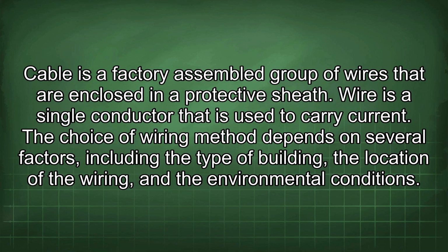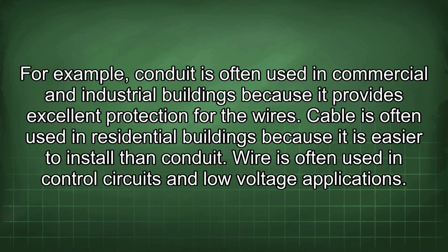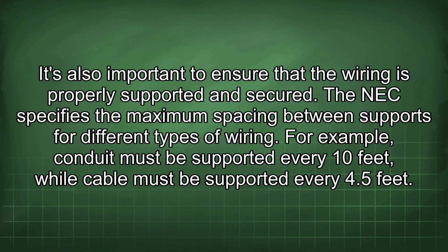The choice of wiring method depends on several factors, including the type of building, the location of the wiring, and the environmental conditions. For example, conduit is often used in commercial and industrial buildings because it provides excellent protection for the wires. Cable is often used in residential buildings because it is easier to install than conduit. Wire is often used in control circuits and low voltage applications. It's also important to ensure that the wiring is properly supported and secured. The NEC specifies the maximum spacing between supports for different types of wiring. For example, conduit must be supported every 10 feet, while cable must be supported every 4.5 feet.